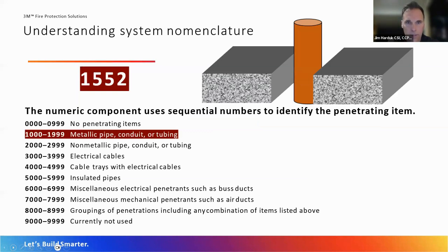And then the numeric component uses a sequential number to identify the penetrating item. So anything that would fall under 1000, that would be no penetrating item. So basically you would just have a large void in a concrete floor or a concrete wall assembly. Anything listed in the 1000 series, that's where you'll find metallic pipe, metallic conduit, or metallic tubing. 2000 series is our non-metallic pipe, non-metallic conduit, and non-metallic tubing. 3000 series is electrical cable. 4000 is cable trays. 5000 is insulated pipe. 6000 series would be miscellaneous electrical penetrants. This would include bus ducts. 7000 series would be your mechanical penetrations. 8000 series are your combos. So basically, in the 8000 series, you could have groupings of any combination of the items above. Next slide.